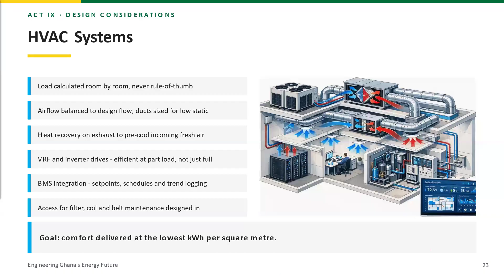So this is all your work: sizing, having the right size of the mechanical system. I'm concerned about how we size, especially our HVAC systems. When we see a space, we think, oh, this space maybe needs 2 horsepower, and we go and buy a 2 horsepower air conditioner to fit the place. Meanwhile, we don't even do a load calculation—what is the energy demand or the cooling load of the space? We don't do that, we just use our eyes to size. But you have to use your pen, you have to do the calculation to size.